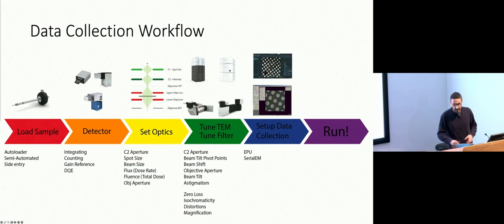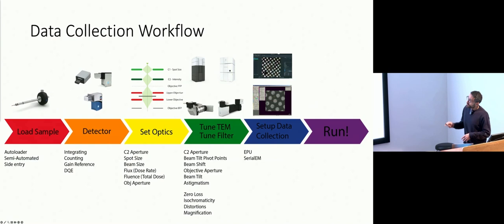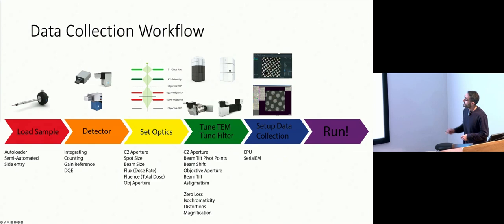Once we have a plan and we want to collect data, a data collection workflow generally looks like this and has six steps. You will be loading the samples — this depends on the type of system, whether an autoloader, a semi-automated system, or a side entry holder. Next, you'll decide the detector and which features to use, then the illumination — we call this setting optics. Then you'll tune the microscope and perhaps the energy filter, decide the software, and eventually press run. And if the microscope doesn't crash, you'll end up with a nice and beautiful dataset the day after.